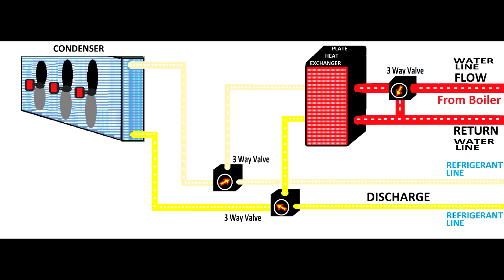And because the system is short of refrigerant, even the fans and the condenser will not work to drop the pressure, because there will not be any pressure to drop.